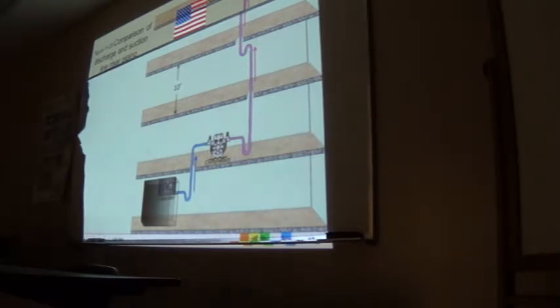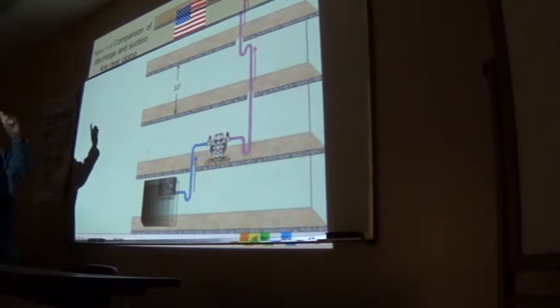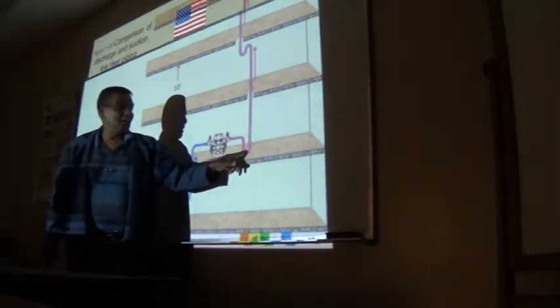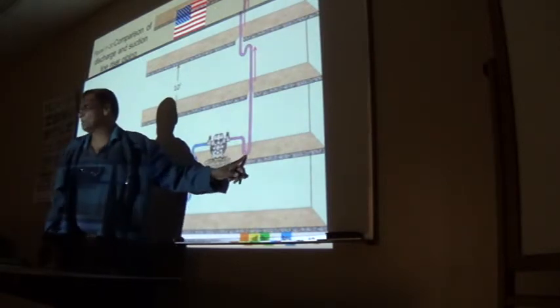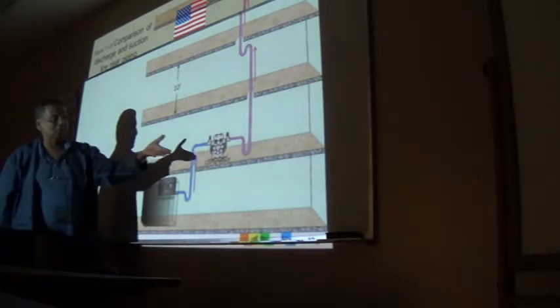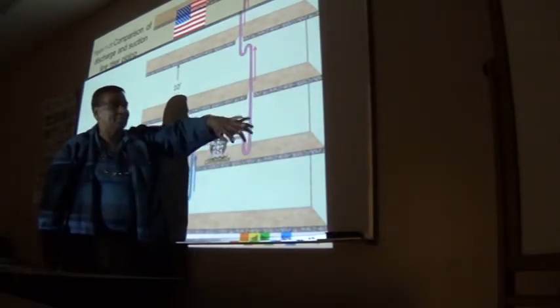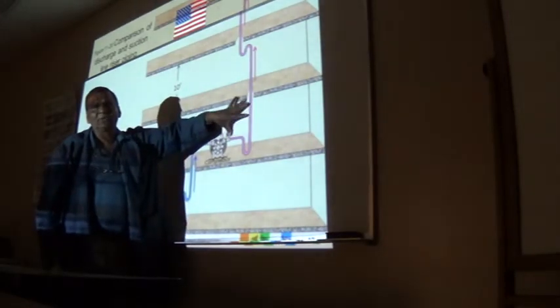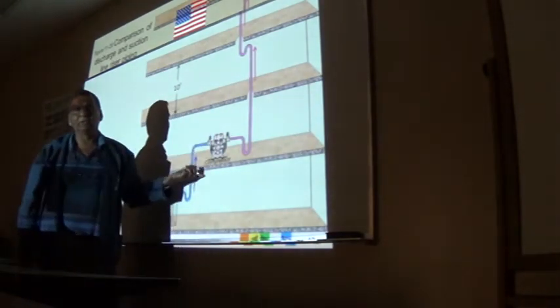Now he's got it on the high side. That's how you pipe it. It's supposed to have a trap. It goes off and it curves down and it goes back up. You always got to tell him to go inverted, right? Yes, that's called a double trap. Now he's got it going up to the condenser too on the high side. Yes. See, here's the thing. I can do two things. I can trap it here on the discharge, because oil will come out with the refrigerant.